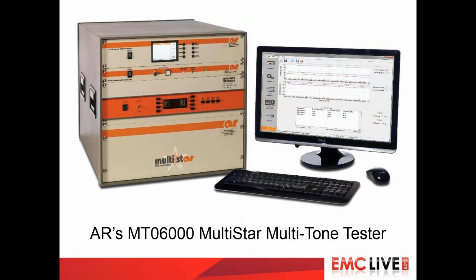So AR has developed this rather unique radiated immunity system. What caught my eye was that it is designed to test up to 10 frequencies at once, so potentially reducing your test time by that factor. And the number of test frequencies can be varied, of course. If anybody has done this kind of testing, you know that it can take several hours to do a thorough test on radiated immunity, depending on the step size. And this multi-tone tester, model MT06000, is an attempt to decrease that test time that normally takes hours, and reduce it way down.